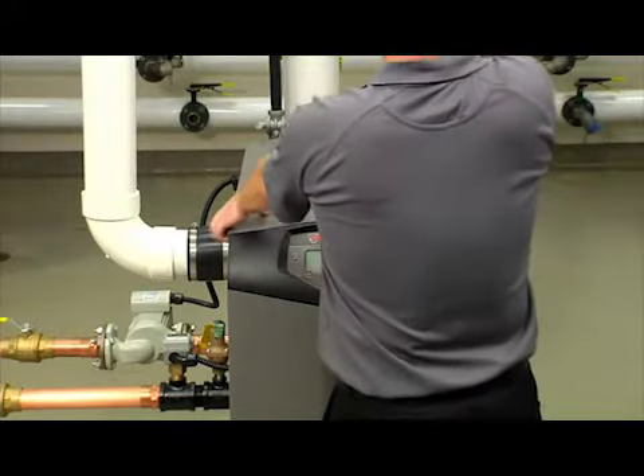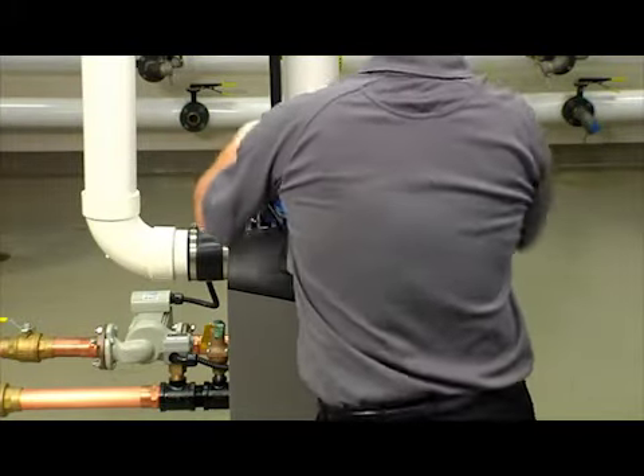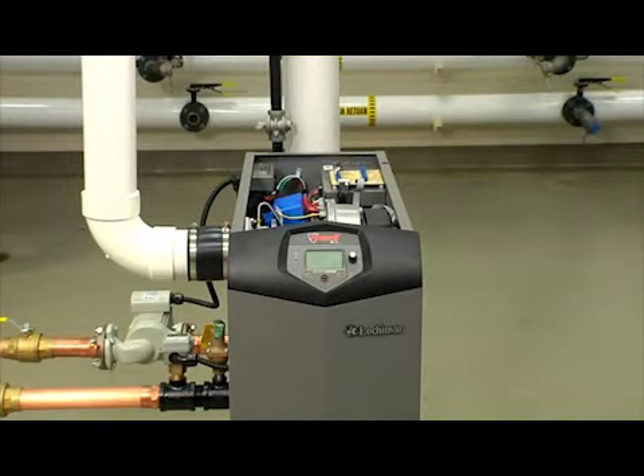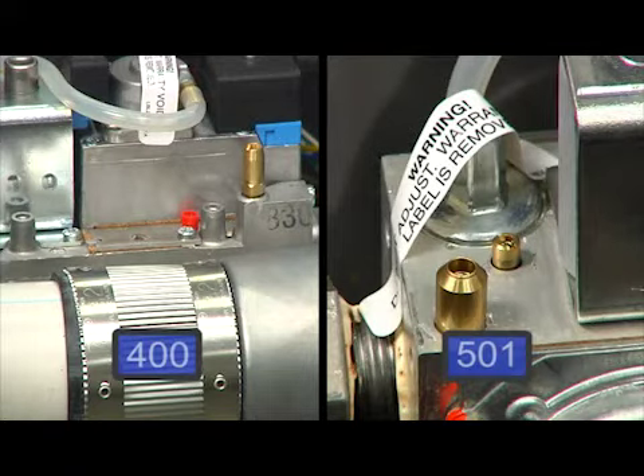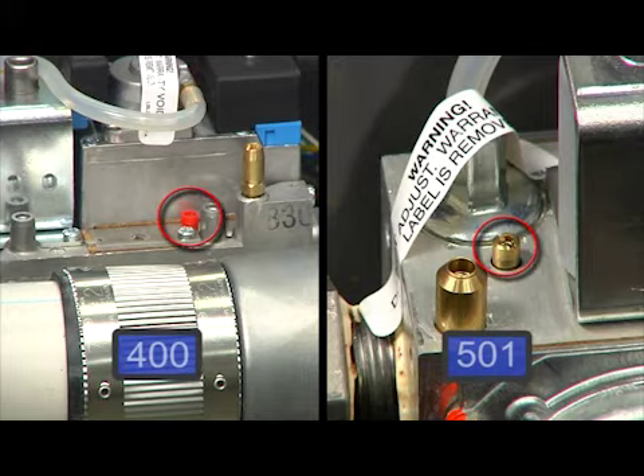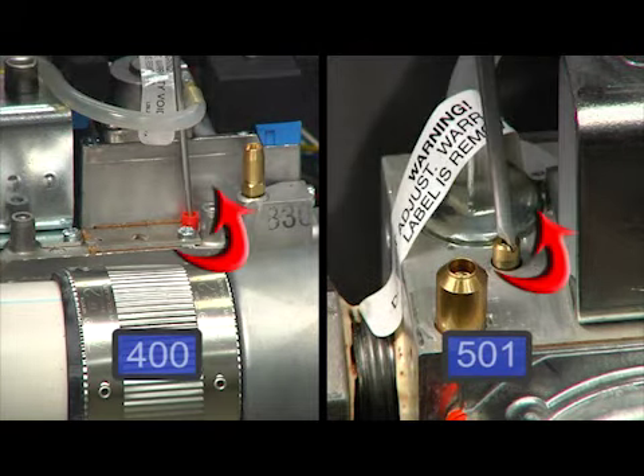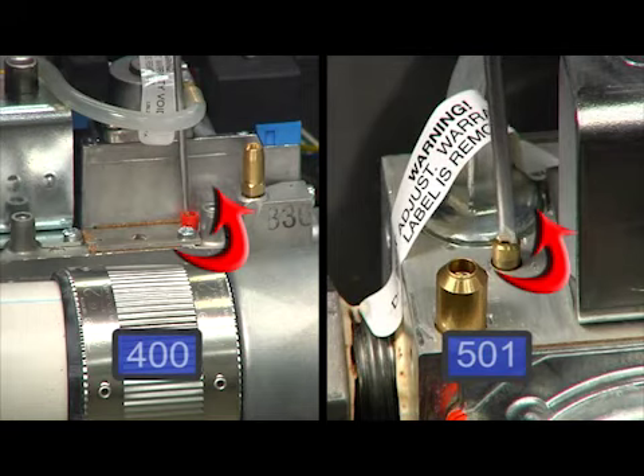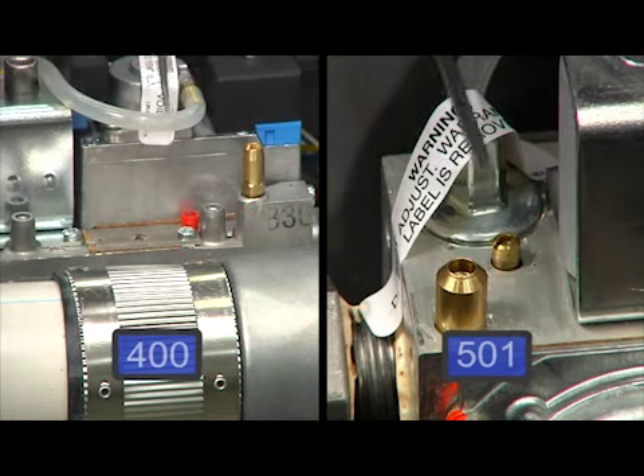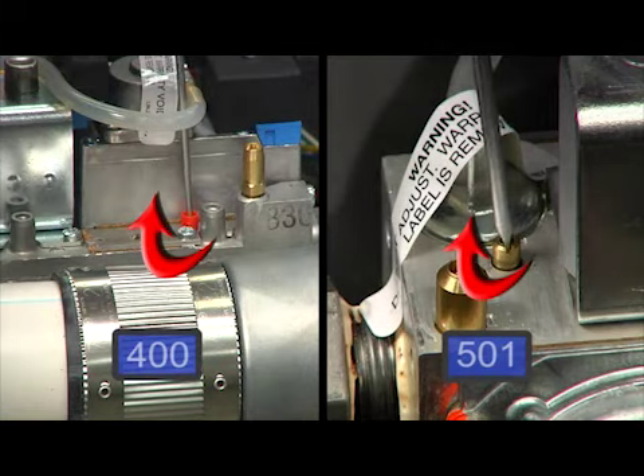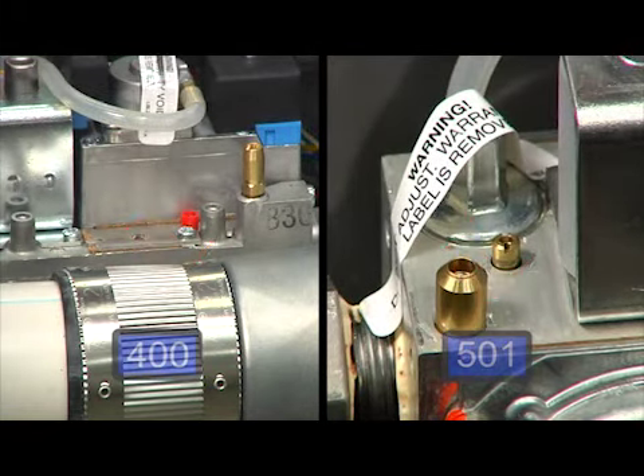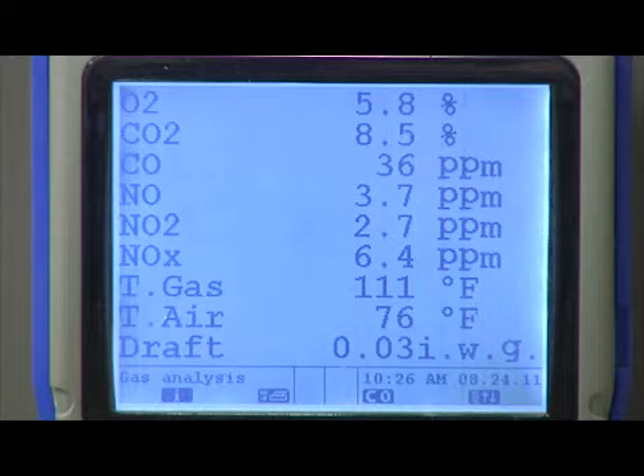Grasp the top panel at the front lower edge. Lift the panel up and pull it away from the unit. For the 400 and 501 models, locate the throttle adjustment screw on top of the gas valve. Using a screwdriver, turn the adjustment screw 1/4 turn counterclockwise to increase CO2 levels, and 1/4 turn clockwise to decrease CO2 levels. After one adjustment of the valve, allow the combustion to stabilize and recheck the CO2 and CO levels.